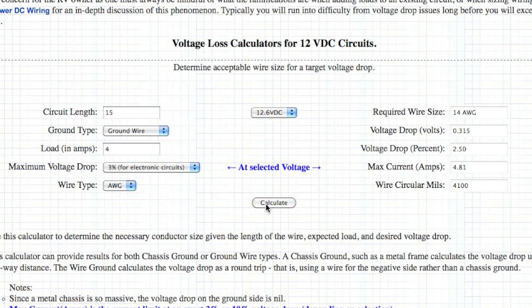Now, we want to do a calculate, and we see here that the recommended wire size is 14 AWG, which is what we're using, and the voltage drop is 0.315 volts or 315 millivolts, and we have a 2.5% voltage drop, which is within our 3% for electronic circuits. And in fact, the maximum current that would stay under 3% would be 4.81 amps. And just as a reference, 4100 circular mils for the wire.